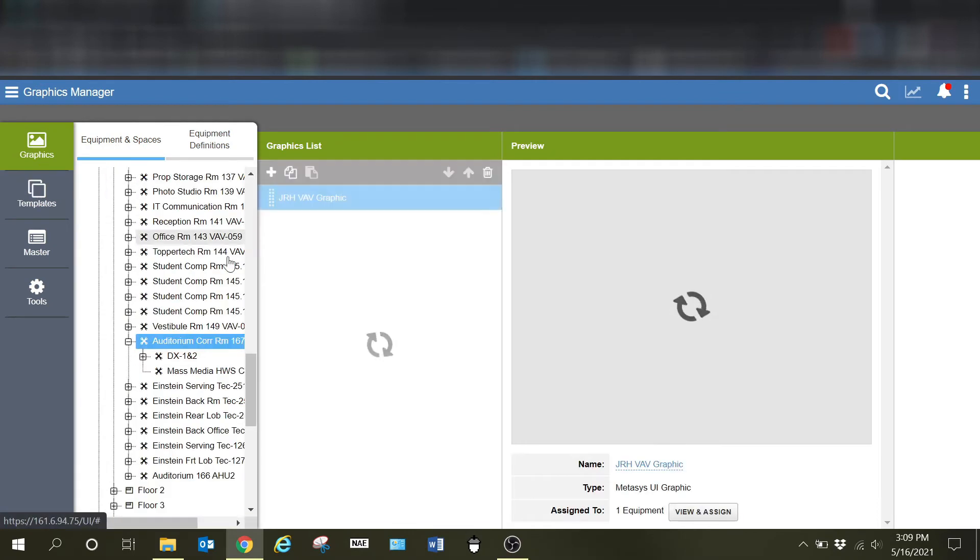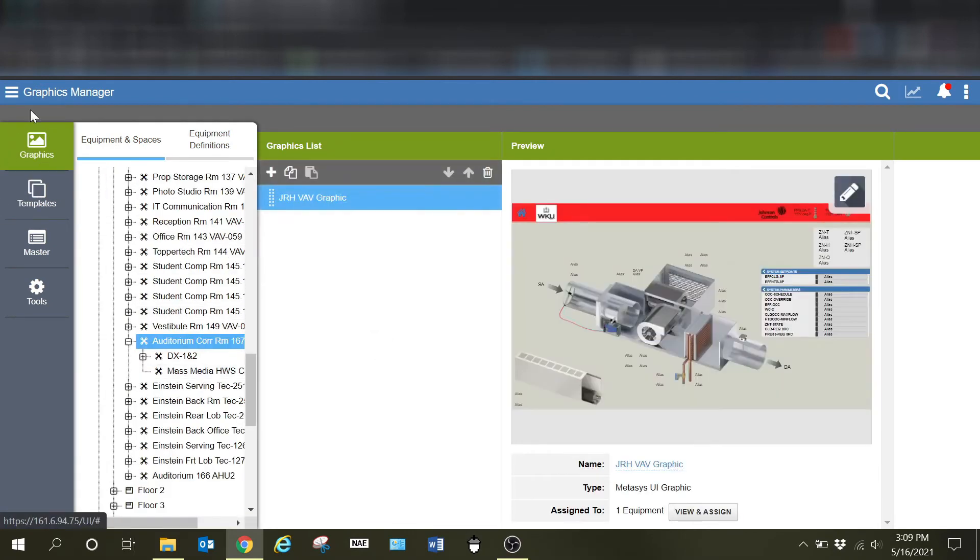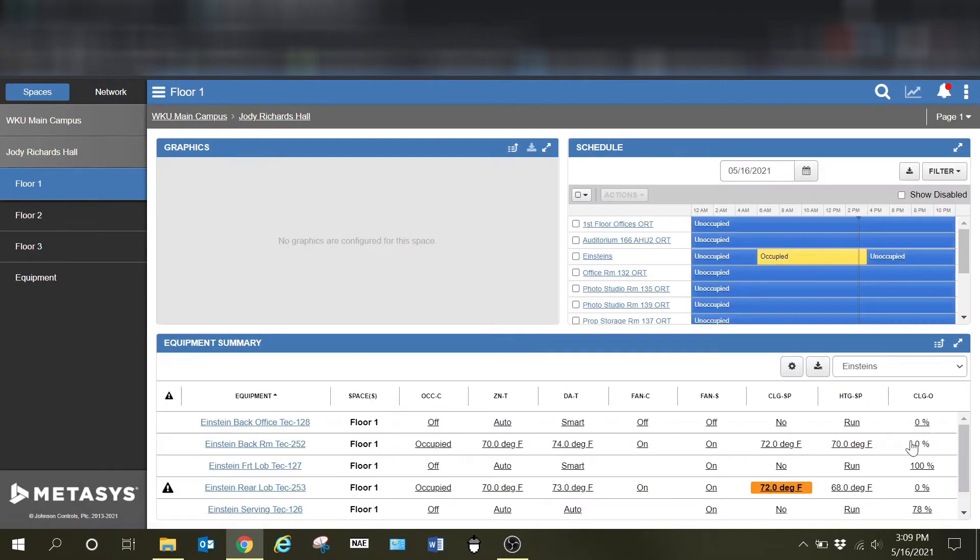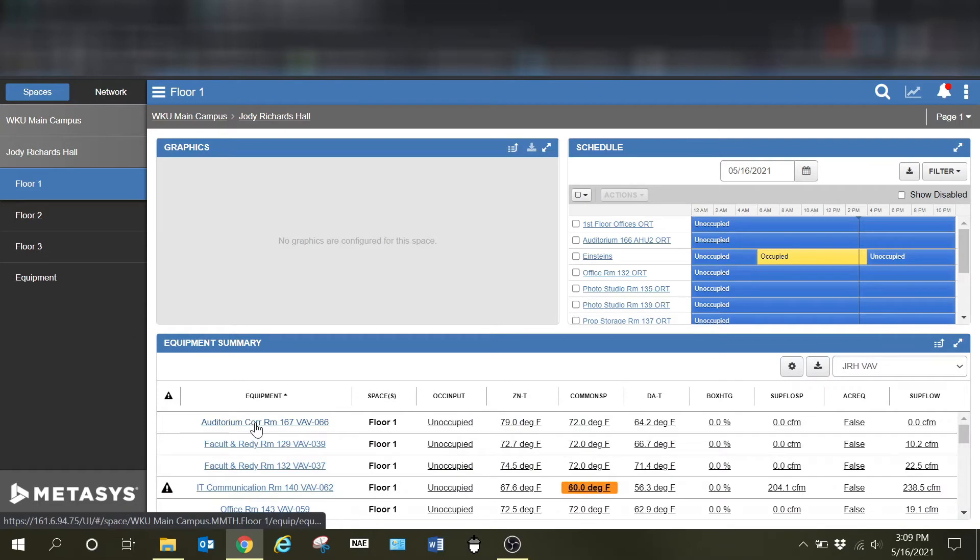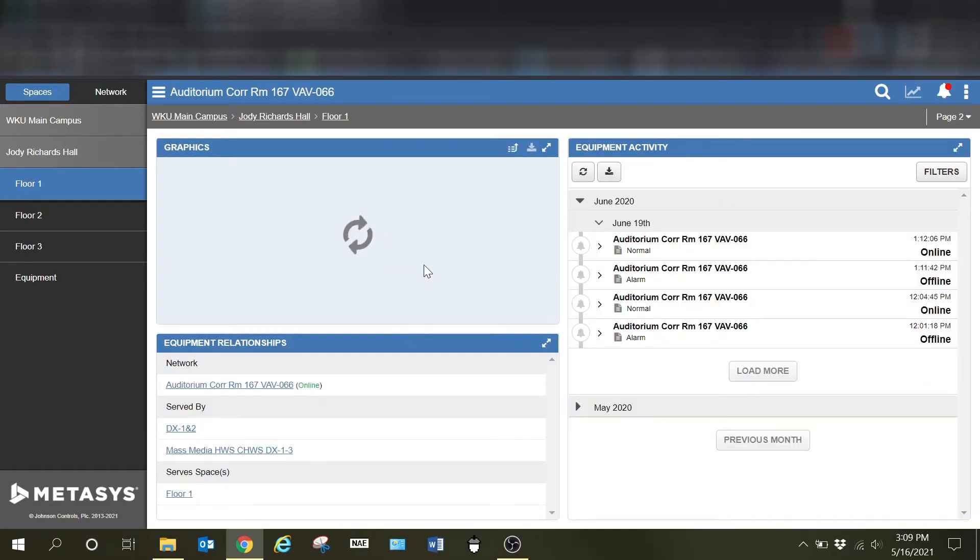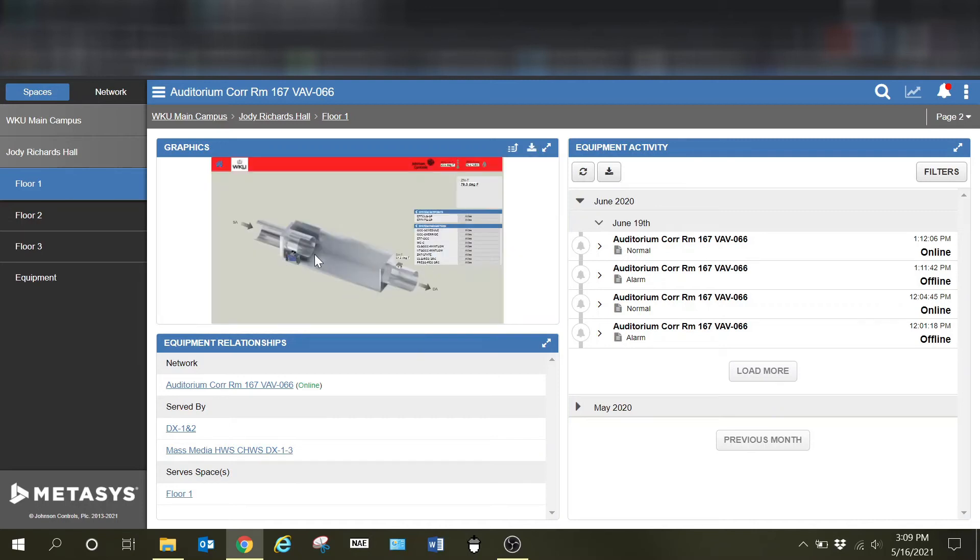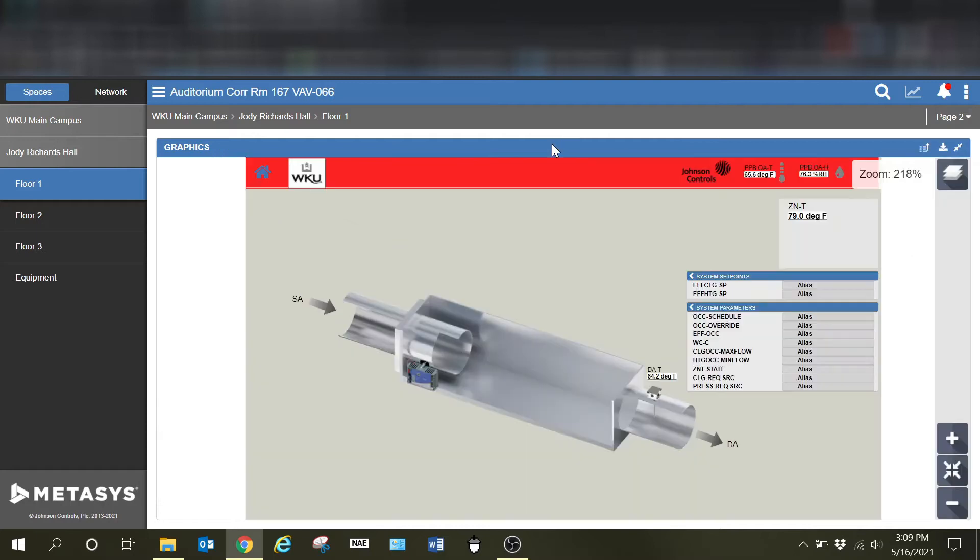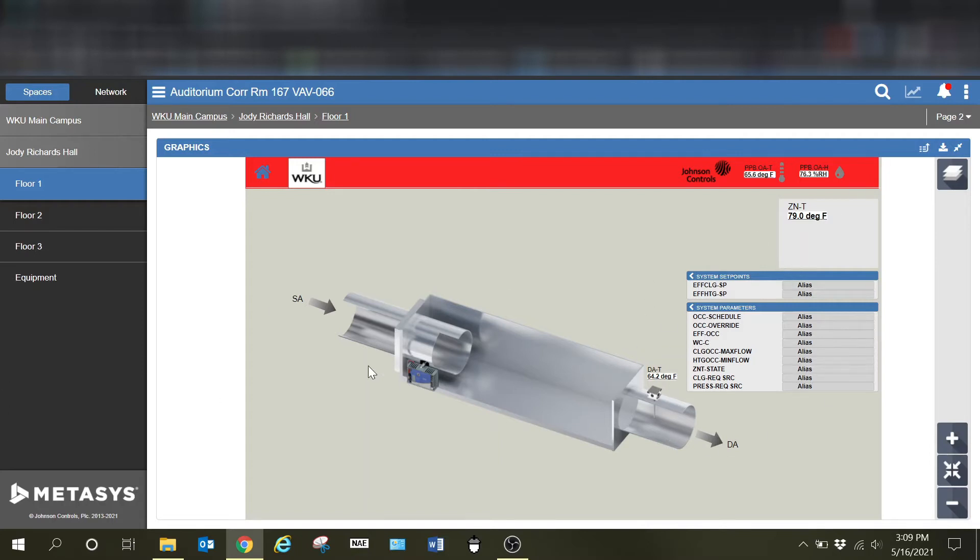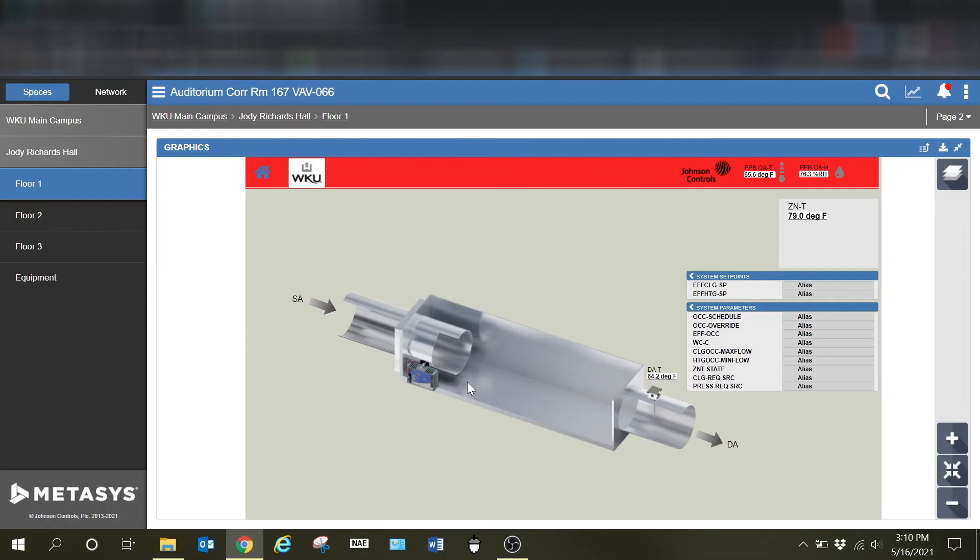I'm going to go right back in here and I'm going to go back to the particular floor, the particular box where I was. Let's drop that down and go right back into it. Very simple. Now that all we did was simply ask it to grab a generic box. And here we are, you can see here, it's just pulled a lot of the information for us. Some of this information is not necessarily used. And you can see here that it just has it aliased and you can go in and customize and do whatever we need to do for this particular device since it's a cooling only box, no reheat or anything like that available. But it did populate some things for us since it knows that it was unable to find anything as far as being a fan powered box, it went ahead and blew all of that out for us. So it's obvious it's not needed. So it got rid of it for us.